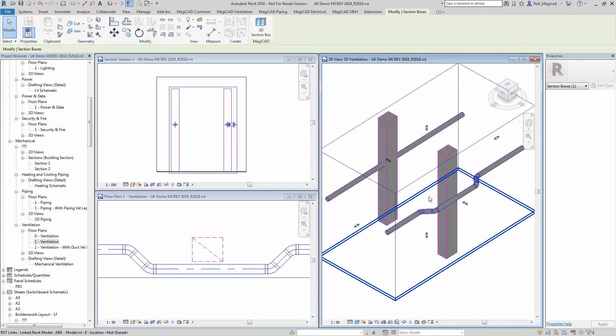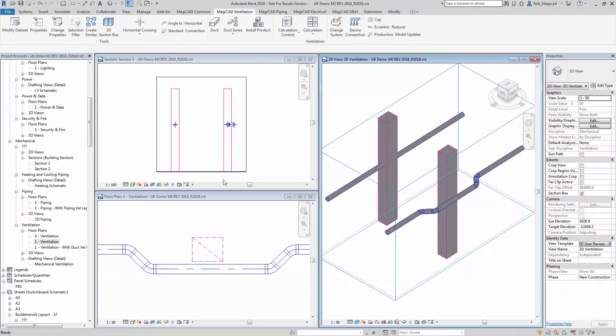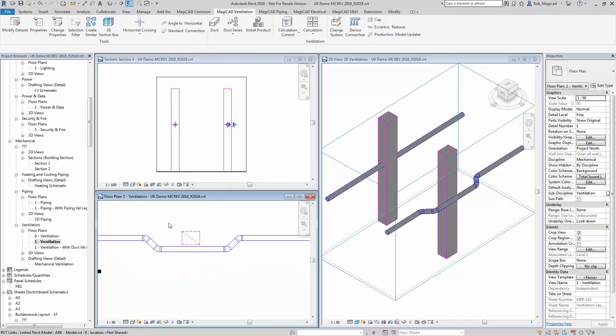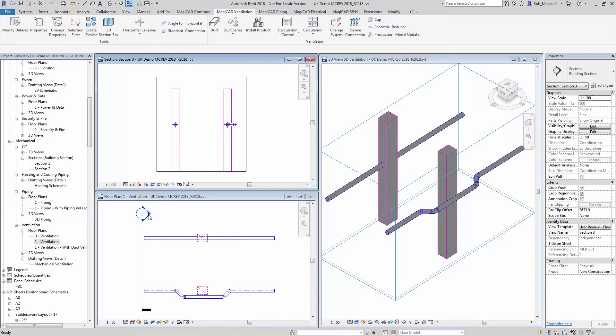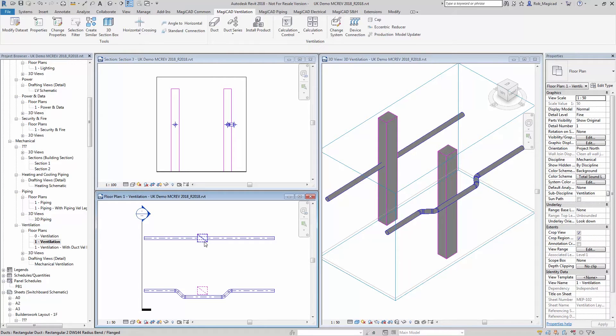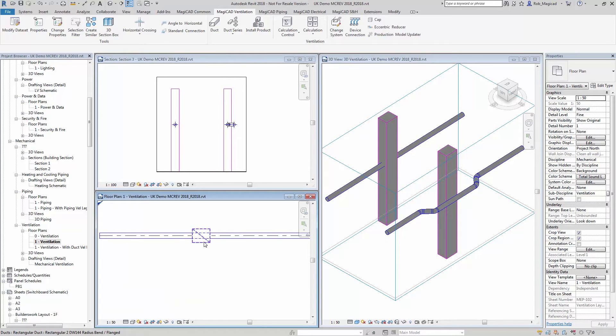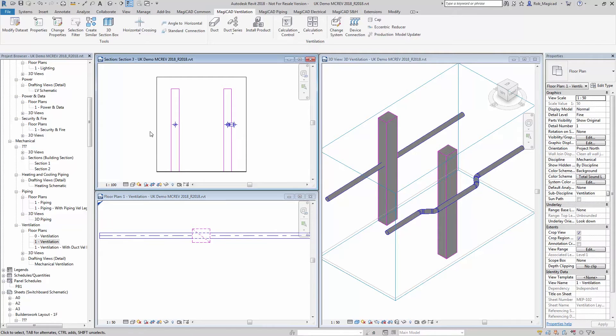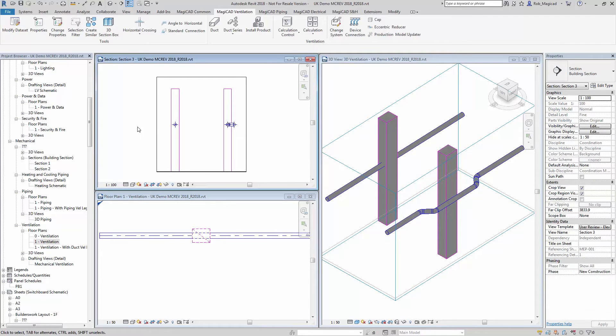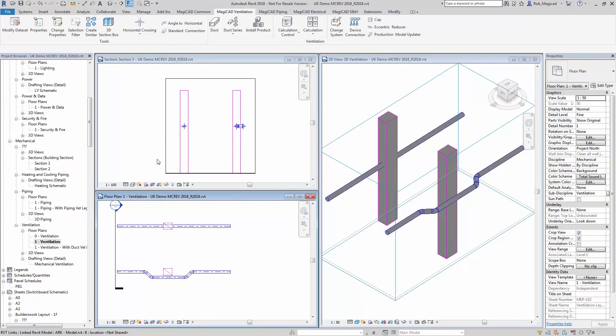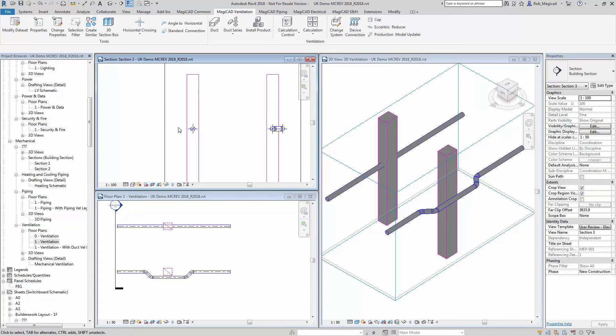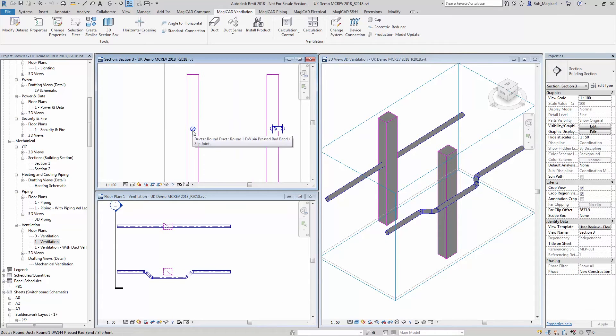The other example of how this can be used as well could be in a section, so if you've got a vertical riser and you wish to offset around other objects that are interfering or colliding with this as it drops down vertically through the building. So in this example, going into this section here, in this view, you can see I've got the rectangular duct here clashing again with the supply duct.